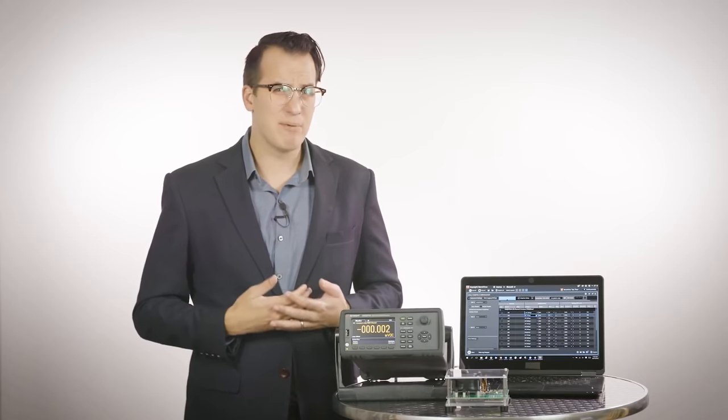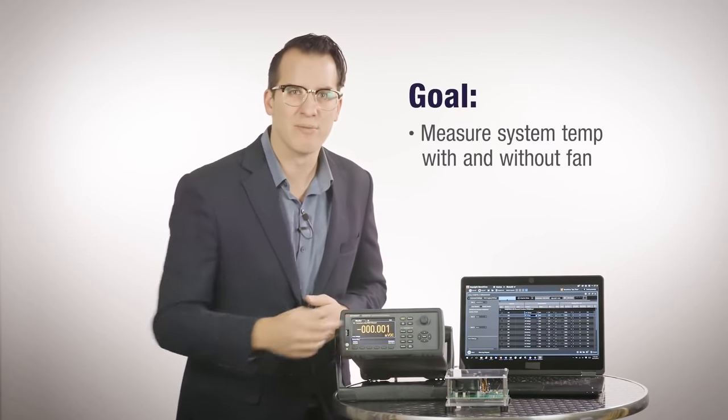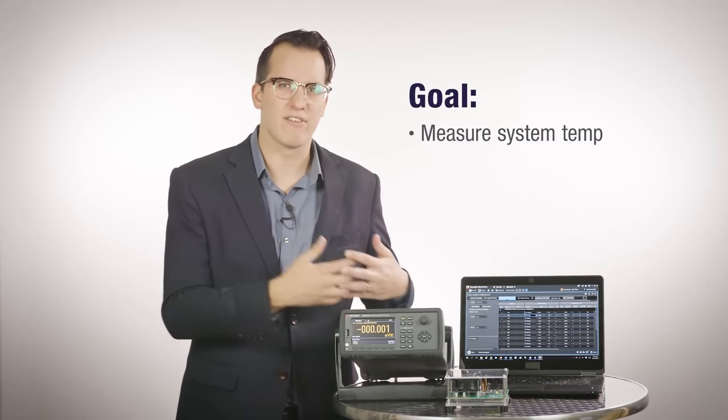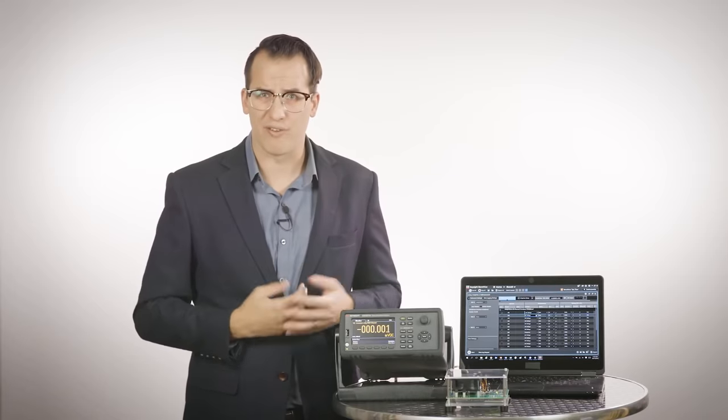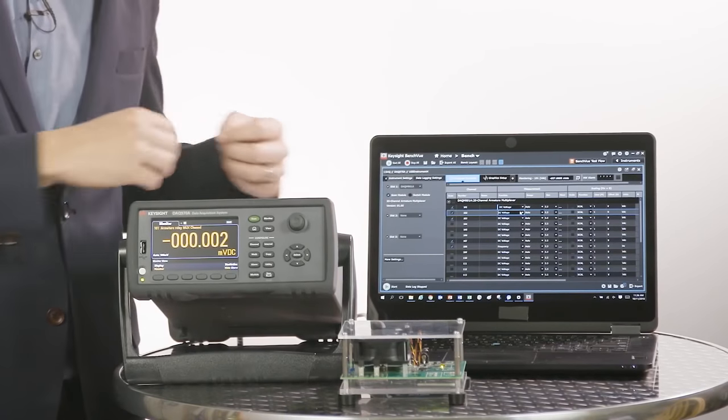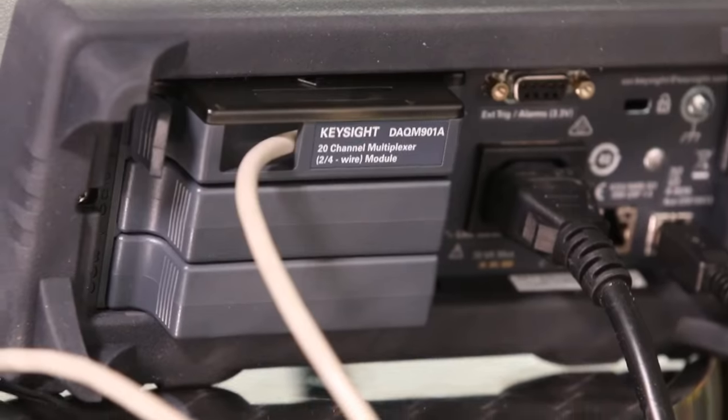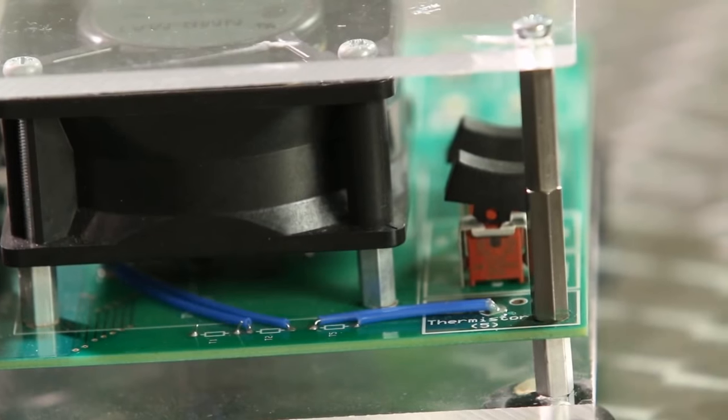Today though, we're going to keep it simple and use just the DAQ to measure a few thermistors on my temperature cube and see how the fan impacts the system temperature. This is a pretty common test that you might have to run on your devices. We're using a DAQ970A and a DAQM901A multiplexer module.